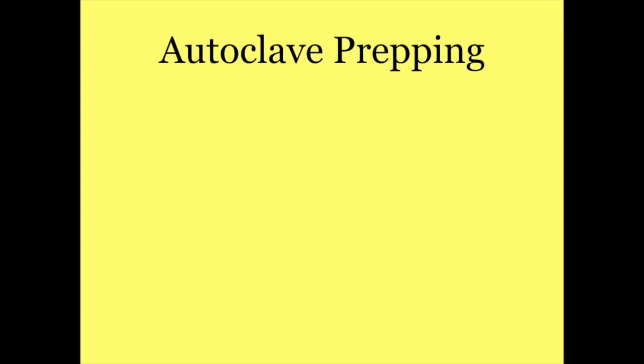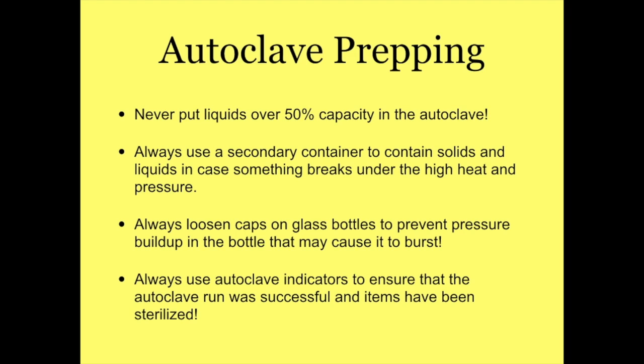Autoclave prepping. Never put liquids over 50% capacity into the autoclave. Always use a secondary container to contain solids and liquids in case something breaks under the high heat and pressure. Always loosen caps on glass bottles to prevent pressure buildup inside the bottle that may cause it to burst. Always use autoclave indicators to ensure that the autoclave run was successful and that the necessary items have been sterilized.